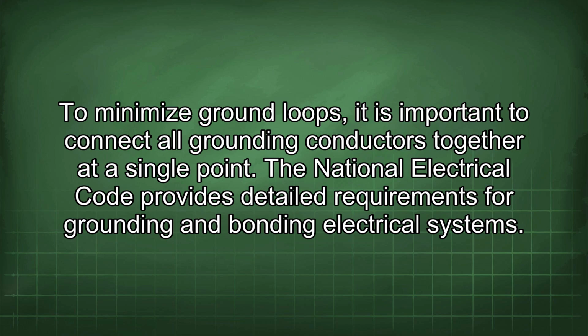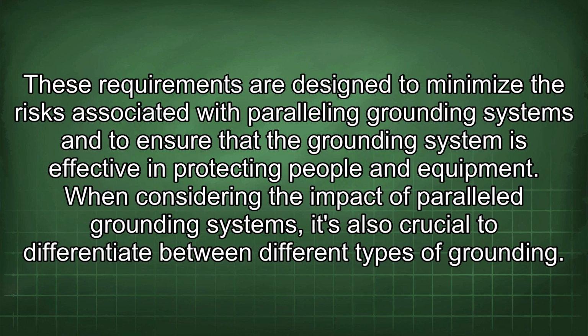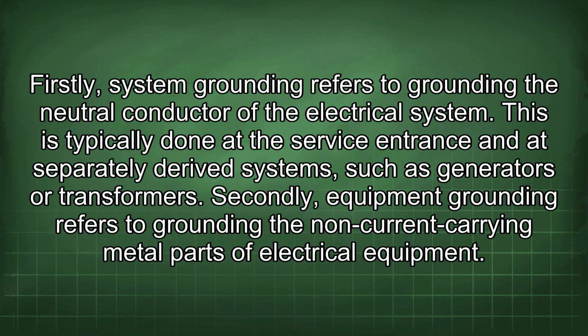The National Electrical Code provides detailed requirements for grounding and bonding electrical systems. These requirements are designed to minimize the risks associated with parallel grounding systems and to ensure that the grounding system is effective in protecting people and equipment. When considering the impact of parallel grounding systems, it's also crucial to differentiate between different types of grounding. Firstly, system grounding refers to grounding the neutral conductor of the electrical system. This is typically done at the service entrance and at separately derived systems such as generators or transformers.